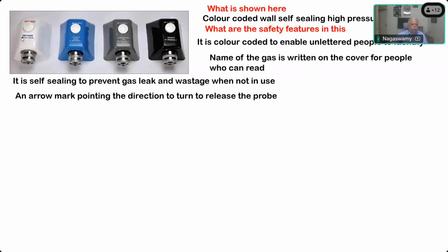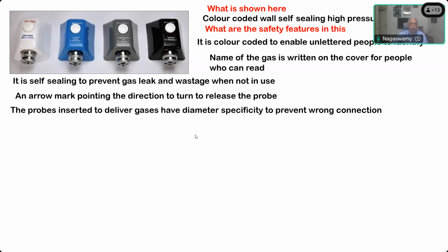Okay, you can see this arrow mark here. Release is written on everything, so that you don't unnecessarily meddle with it and try to unplug or remove the probe that is going to be inserted. So four points you have to know: color coded, name of the gas written, self-sealing to prevent gas leak, and arrow mark pointing the direction to turn to release the probe. Also, probes inserted to deliver gases have diameter specificity to prevent wrong connection. Okay, so that is the thing.